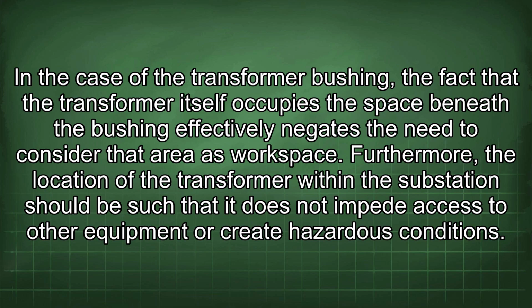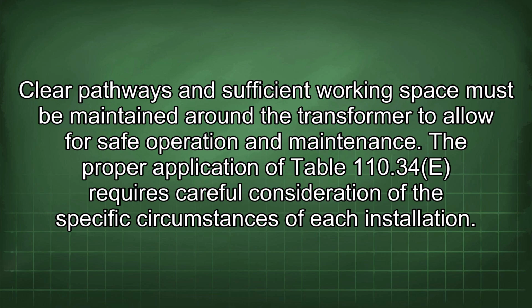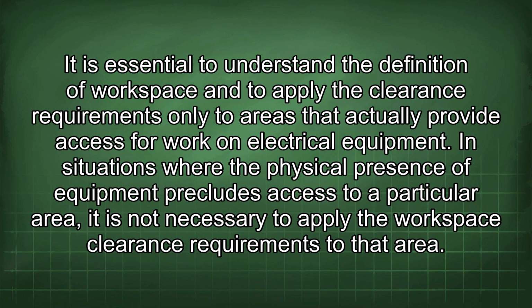Furthermore, the location of the transformer within the substation should be such that it does not impede access to other equipment or create hazardous conditions. Clear pathways and sufficient working space must be maintained around the transformer to allow for safe operation and maintenance. The proper application of Table 110.34(E) requires careful consideration of the specific circumstances of each installation. It is essential to understand the definition of workspace and to apply clearance requirements only to areas that actually provide access for work on electrical equipment. In situations where the physical presence of equipment precludes access to a particular area, it is not necessary to apply the workspace clearance requirements to that area.